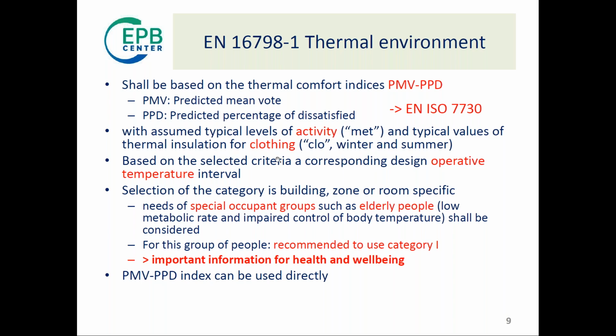Based on the selected criteria, the standard focuses on the operative temperature. There is an interval given for each of the categories we saw before. One important thing is that the selection of the category is not necessarily done for a whole building under investigation, but can be done zone by zone or room by room, depending on what is going on in those parts of a building.